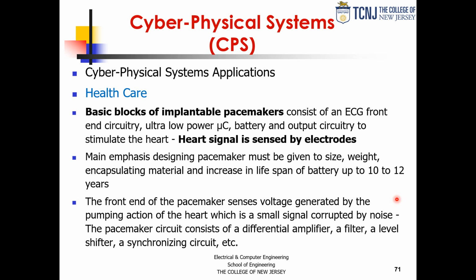We have to filter out the main source of noise in the human body, which is actually 60 hertz from the environment. So for all medical devices, the first thing they do is have a very good 60 hertz noise suppression filter. It's really a notch type filter where you are trying to take out the 60 hertz. But that's the biggest contributor of noise in the human body. We pick it up from the wires. Okay? So it looks sort of like that, right?